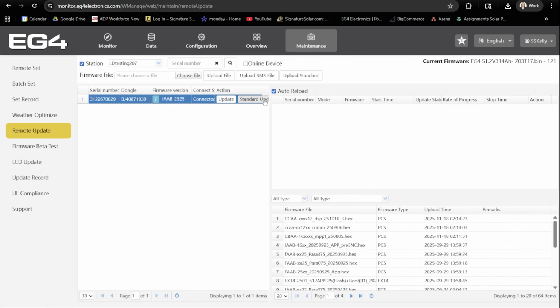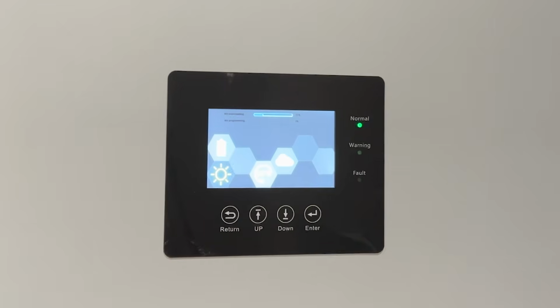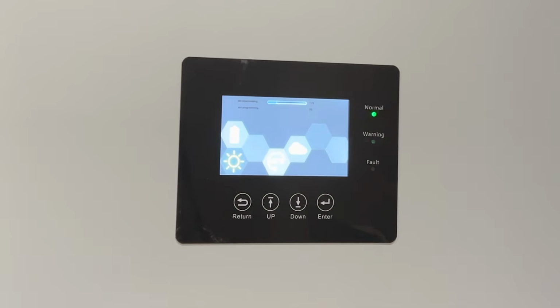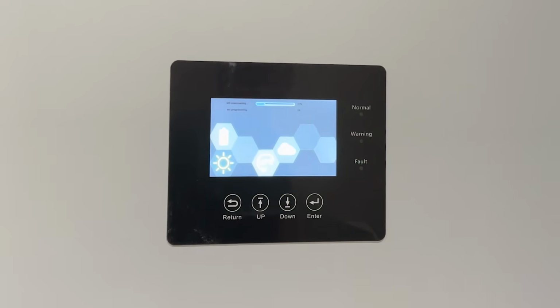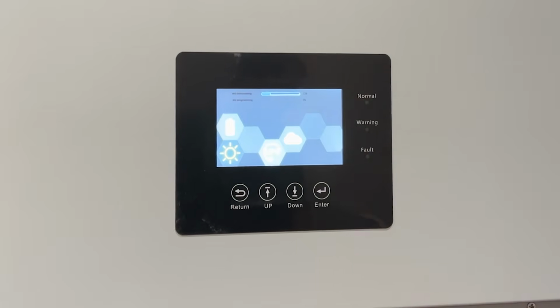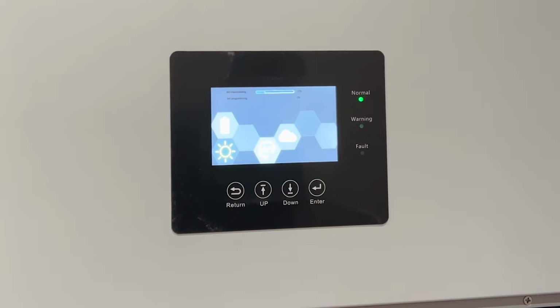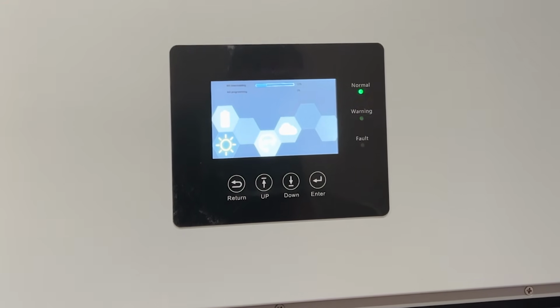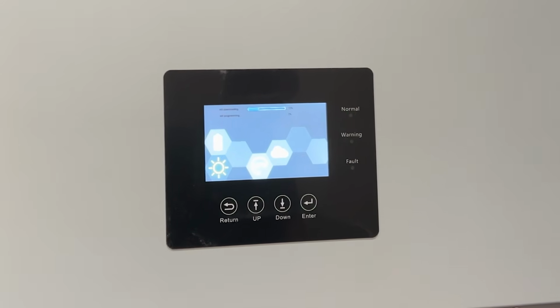At this point, you will see a progress bar. It is important to understand that this progress bar represents the firmware downloading to the inverter, not directly to the battery. Once the file has successfully downloaded to the inverter, the system will show a success status. After this, the inverter begins transferring the firmware to the battery. During this phase, do not cancel the update and do not power off the inverter or the battery. Interrupting power during this transfer can cause the update to fail.